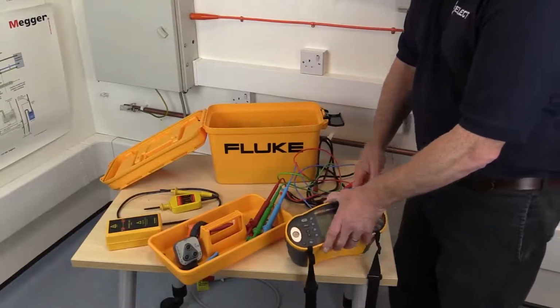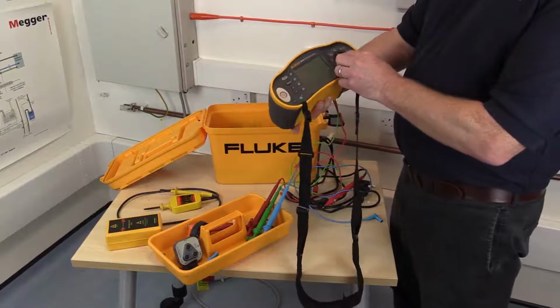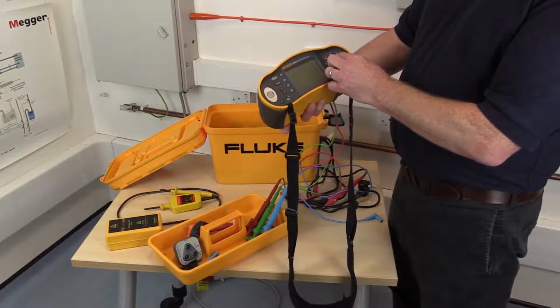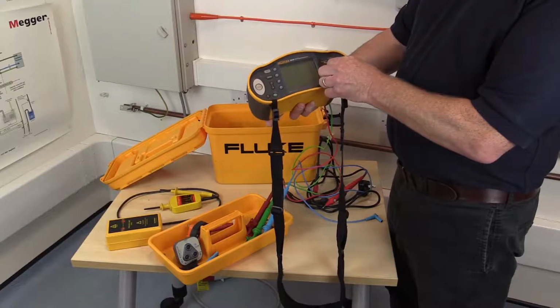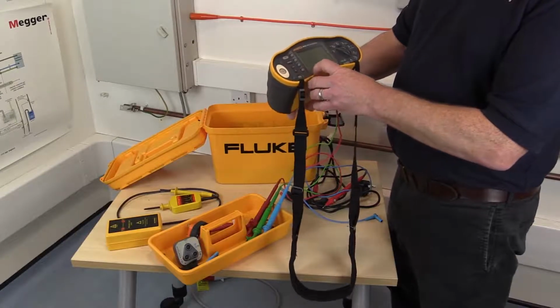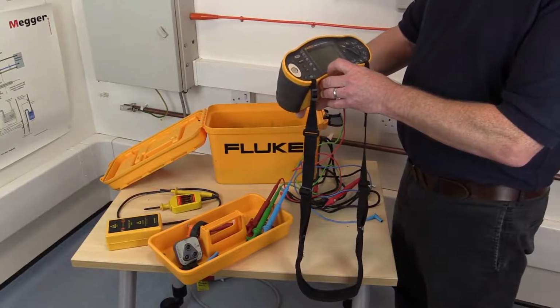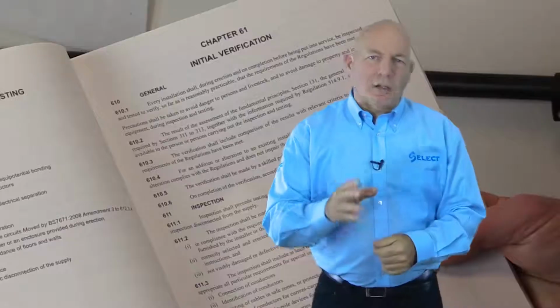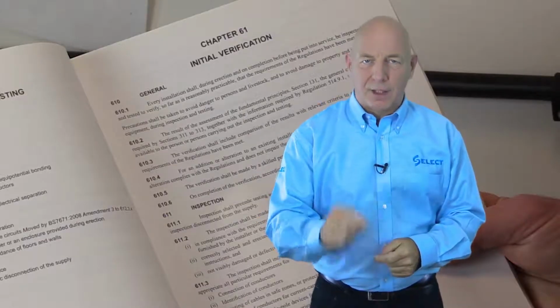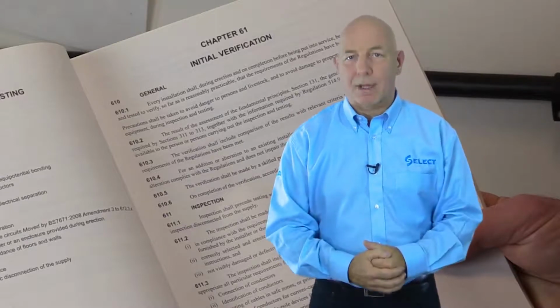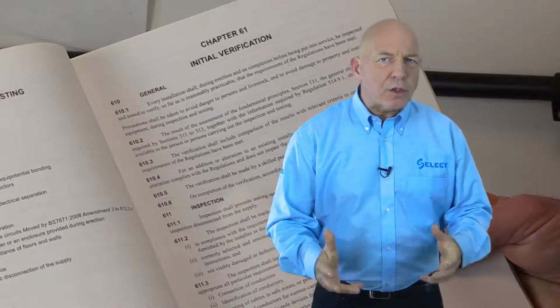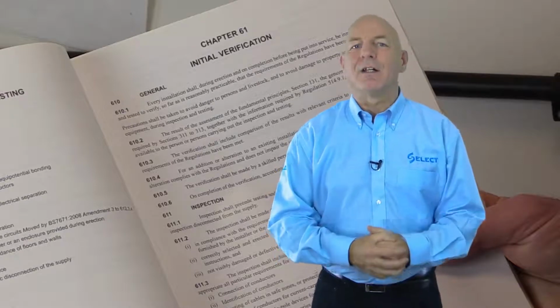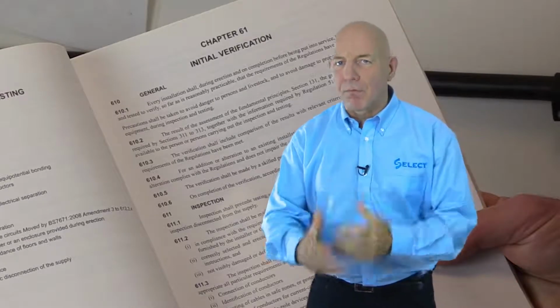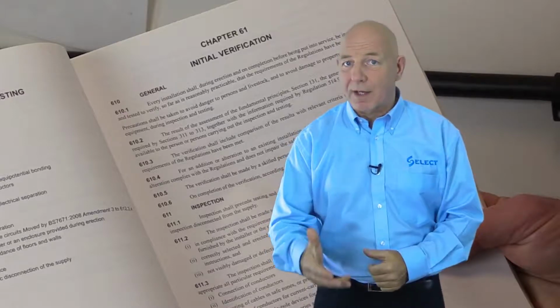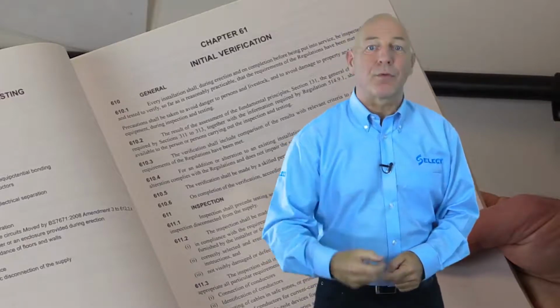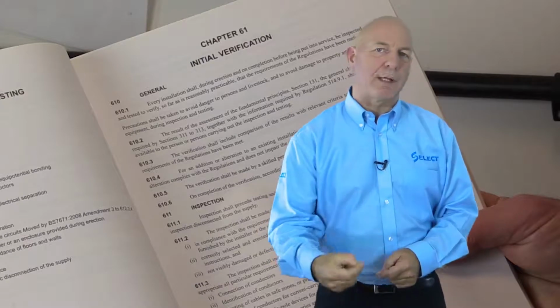Now you should note here, a good working knowledge of the operation of the test instrument, including selection of the correct test function and scale, is also very important to ensure correct and accurate test information is obtained. It's also very important that the correct sequence is followed as required in Chapter 61. Inspection should always precede testing, and initial testing should be carried out before the installation is energized, and then any tests necessary with the installation energized should then be carried out.